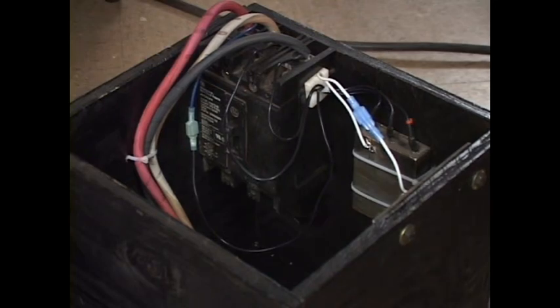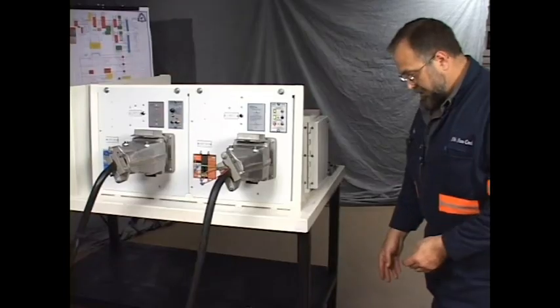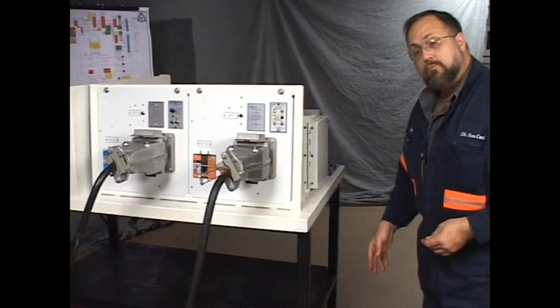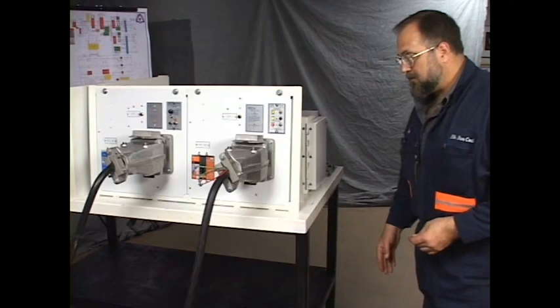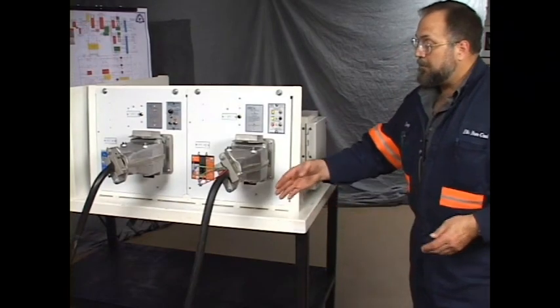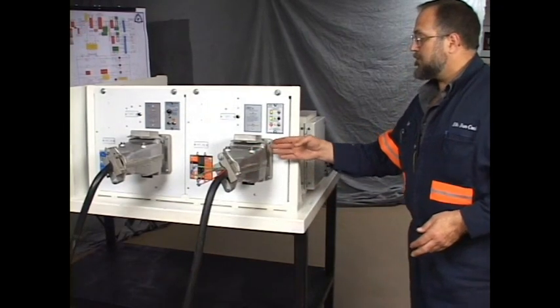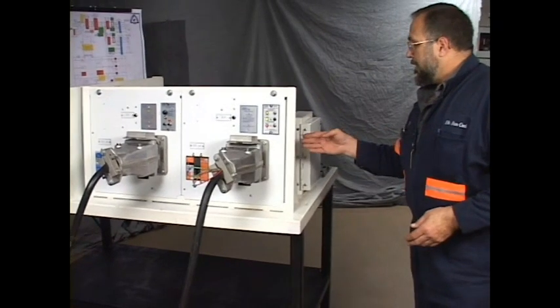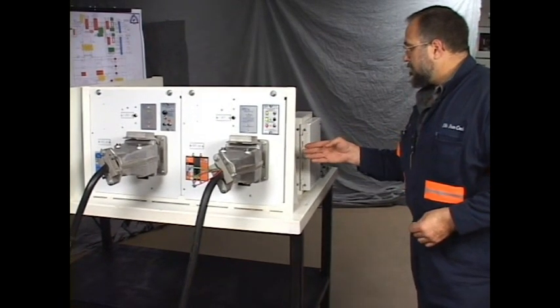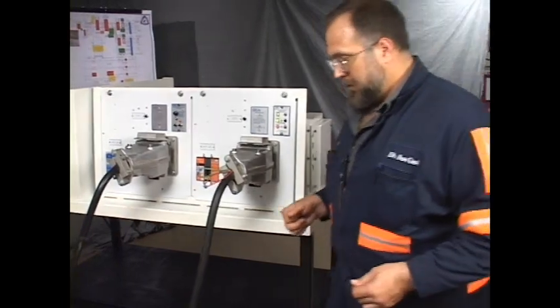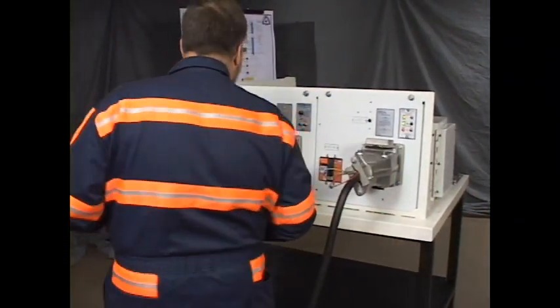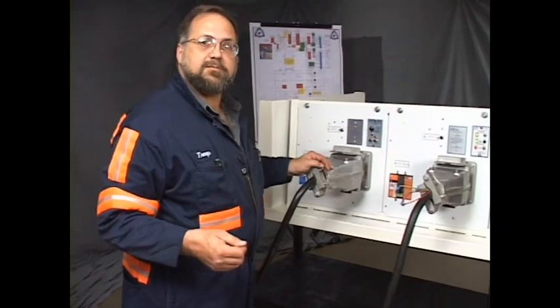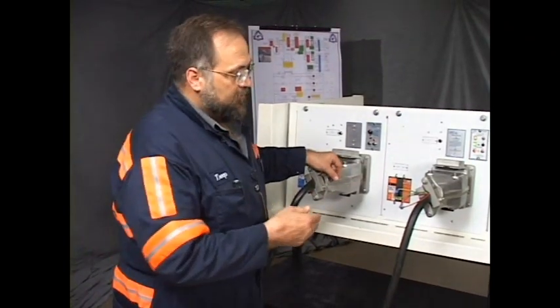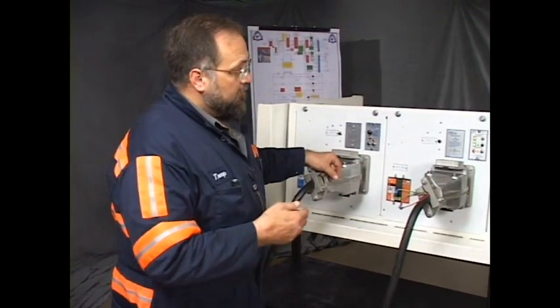Now, when the white wire leaves the filter, it's attached to the frame of the machine, and you know the frame ground wire is attached to the frame. So that signal is put on the ground wire, sent back up the cable to the coupler, through the receptacle, and when it passes through the receptacle on the conductor, there's a CT. It picks that signal up, or it recognizes that signal.